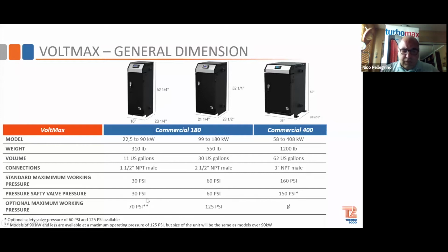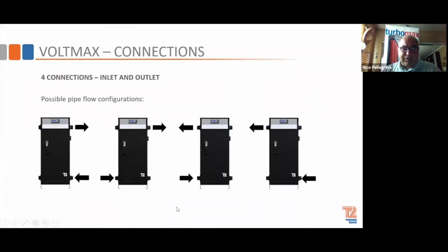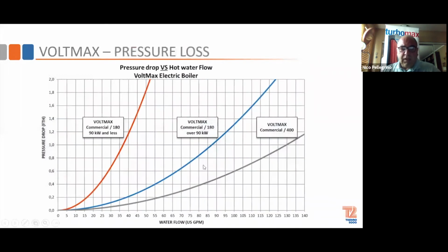The other thing is there are some options available in some of the boilers. Some engineers will want a higher PSI, or if you get head pressure from a building, each one has to be ordered to the rate of PSI needed. As I said, 4 connections in and out. The only thing here is that the supply always has to come off the top of the boiler, because that's where the elements are, and the flow sensors and everything else is on top of the boilers. So built-in curves show the pressure loss. As I said, we're a tank, not a heat exchanger, so you can see very, very little pressure drop across big flow rates on our boilers.